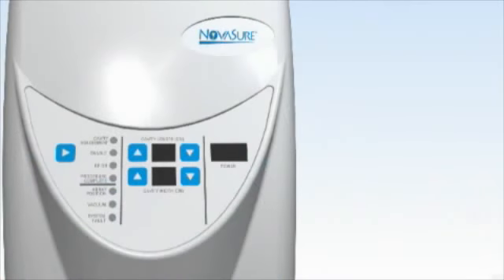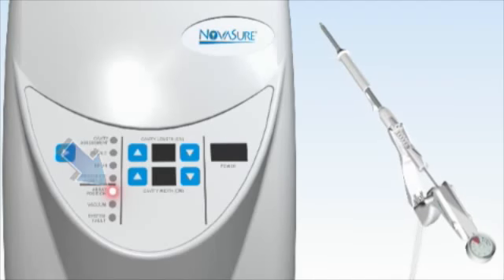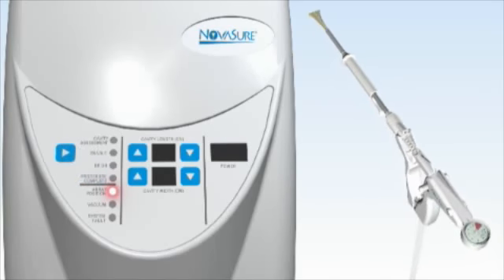Once connected, you should hear an audible beep in conjunction with a flashing red cavity assessment LED on the front of the NovaSure RF controller. This indicates that the air is being purged from the vacuum suction lines. Once this process is complete, it is safe for the physician to insert the disposable device into the patient. When plugging the disposable device in, you should also notice a red LED appear next to array position on the front of the NovaSure RF controller. This LED should extinguish once the NovaSure disposable device is deployed by the physician.